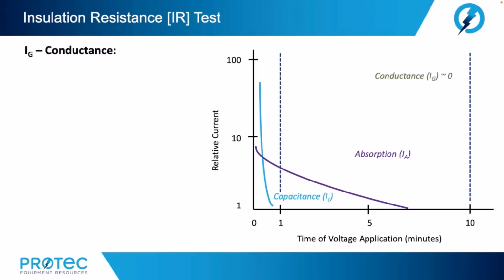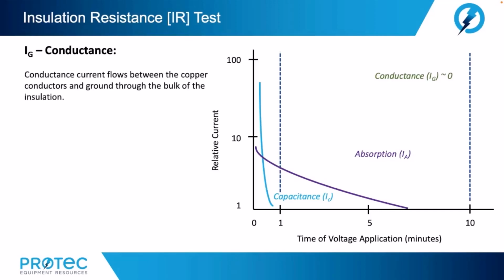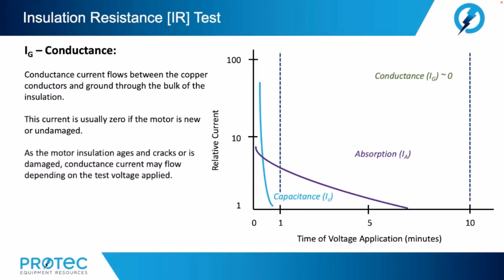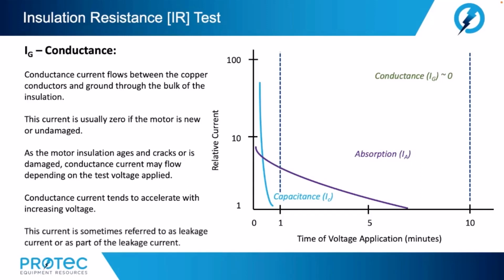We also have a thing called conductance or conductive current. Conductance current flows between the copper conductors and ground through the bulk of the insulation. Now, this current is usually zero if the motor is new or is undamaged. As the motor insulation ages and cracks or is damaged, conductance current may flow depending on the test voltage that is applied. Conductance current tends to accelerate with increasing voltage. This current is sometimes referred to as leakage current or as part of the leakage current.